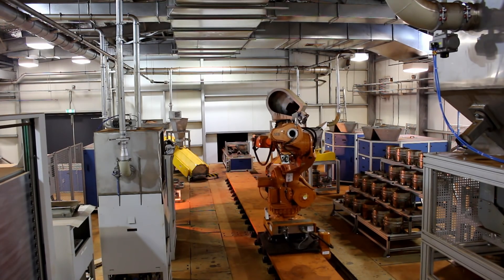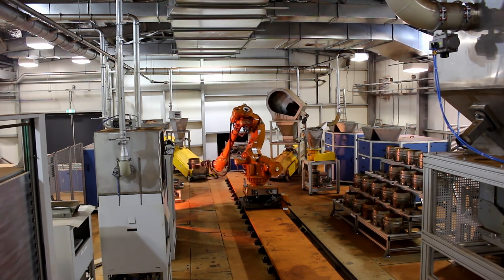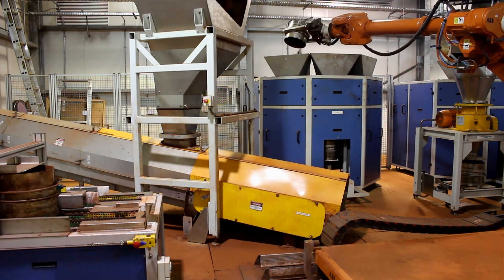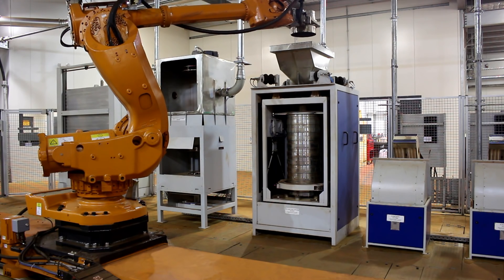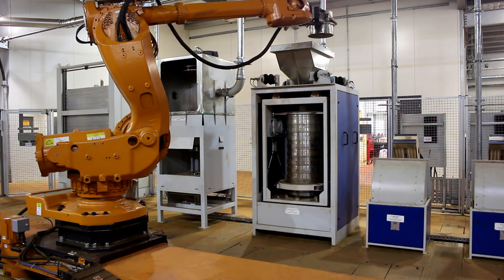A single large ABB robot arm moving back and forth on a track handles all of the samples when they arrive at the laboratory. Samples are split into various aliquots. One aliquot is used for moisture determination according to ISO 3087, while a different aliquot is used to determine the particle size of the product conforming to ISO 4701, utilizing an automated sieve shaker.